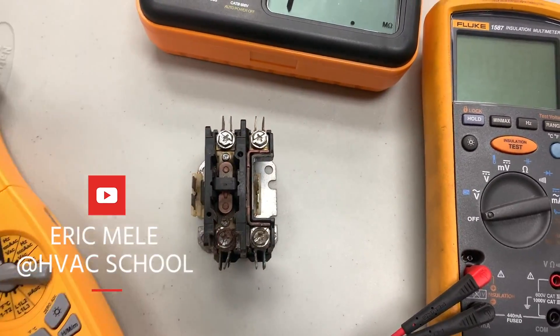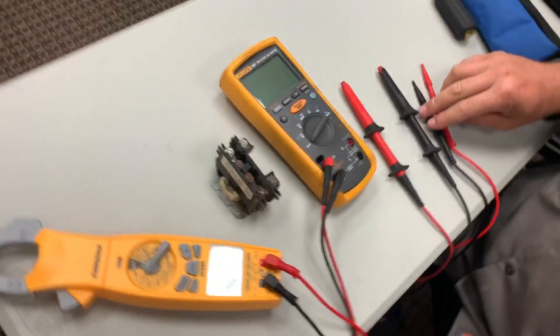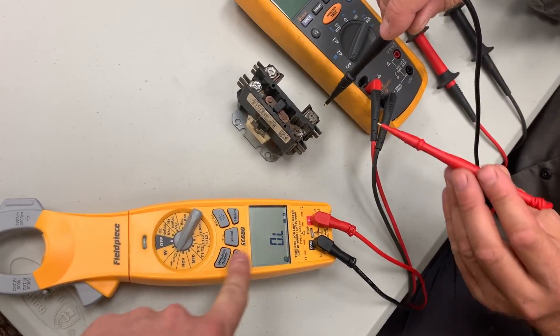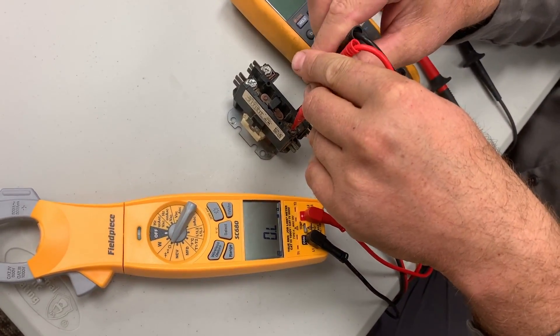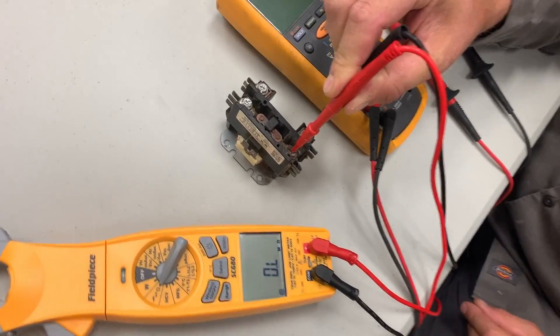Eric is going to demonstrate. We're going to start with the Fieldpiece meter and leave it in megaohm scale. We've got the screws a little bit backed out because that's how it was when we uninstalled it. So when we first checked it, we were like, no, it's not shorted.